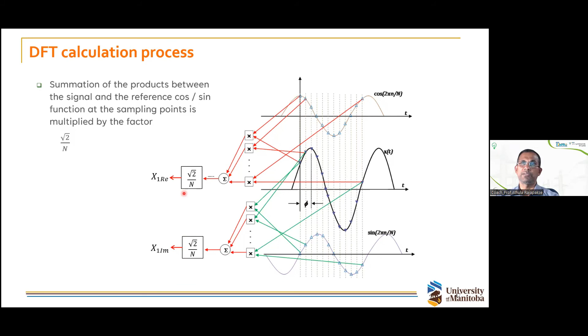Of course, now if you take one set of samples, then you can compute this, that is fine. But in a PMU or protection system, we need to do this continuously, right? So you have to repeat this same calculation after taking a new data window, which may be shifted by one sampling point, right? So if you compute the first phasor, let's say we get this one based on our definition, where I put the cosine and sine parts together over here. When you compute from the next window, you get this one, right?